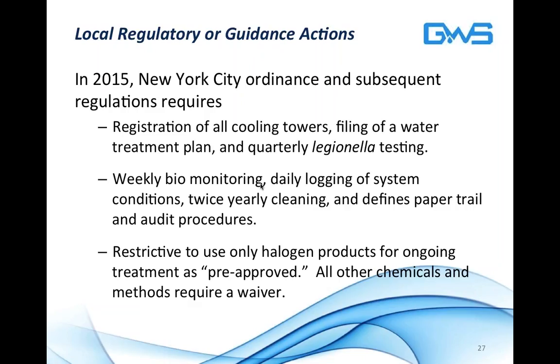However, the New York City regulations went much further, requiring weekly biomonitoring, total bacteria counts, daily logging of system conditions including conductivity and other indicators, twice-yearly cleaning, and they define very specifically a paper trail and audit procedures for the same.